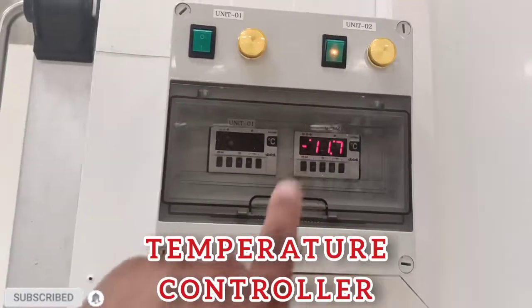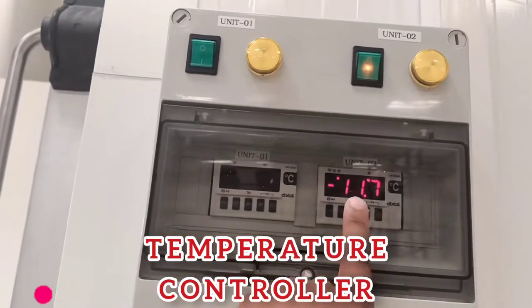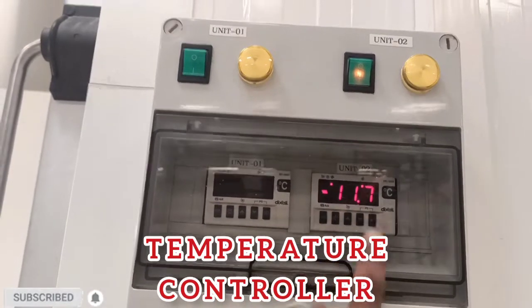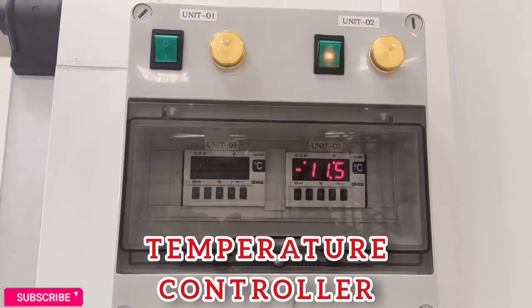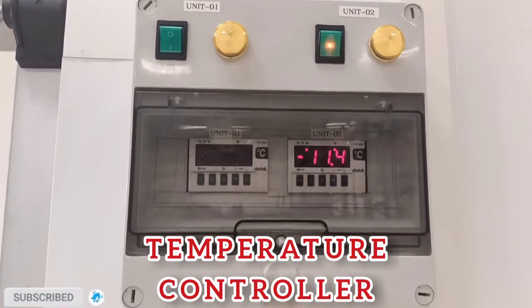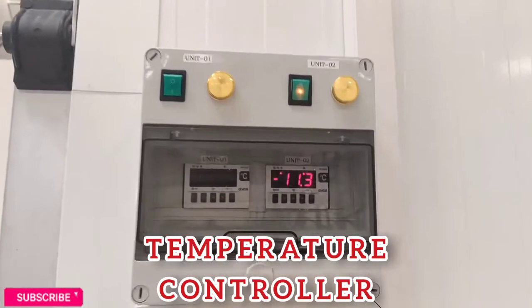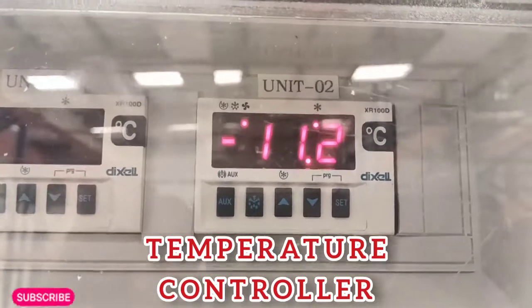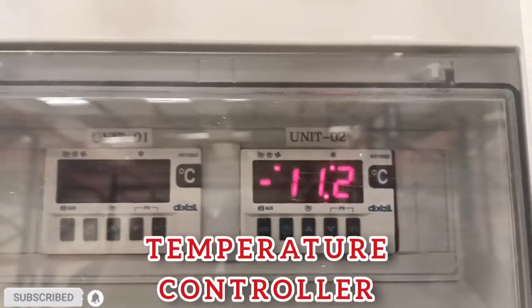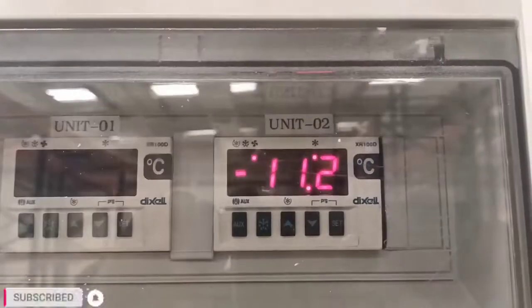You see this? This is temperature minus 11.7. One unit is standby and one unit is continue running. This is minus 11.2 Freezer. Our required temperature is minus 25.